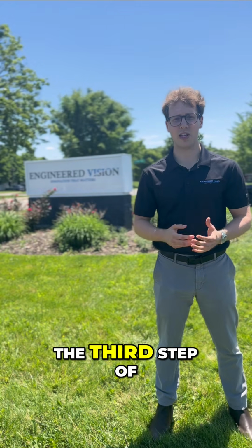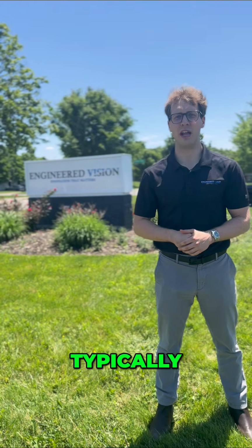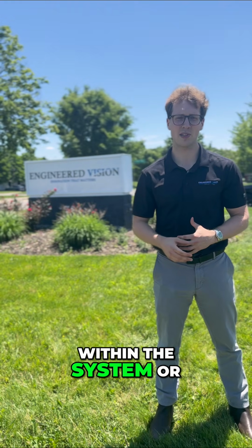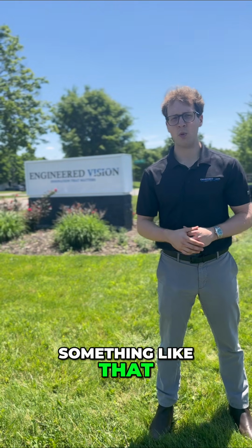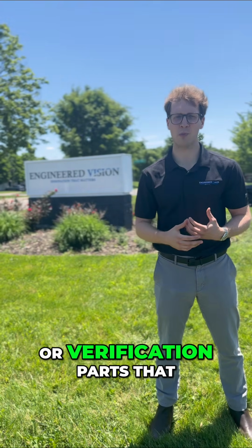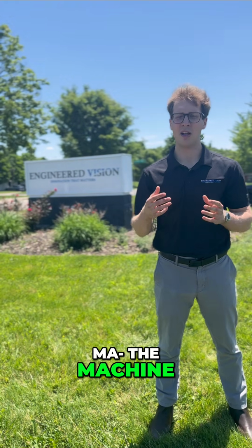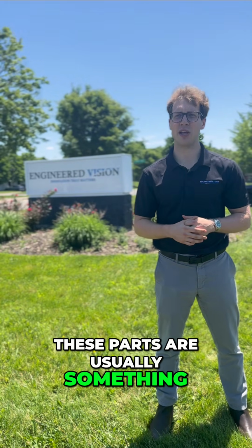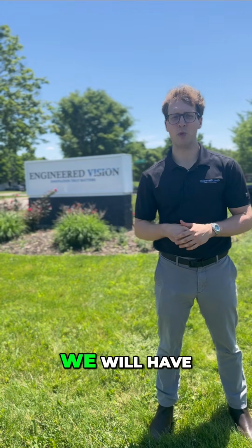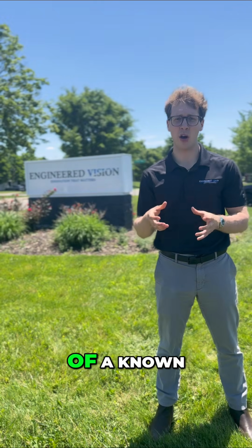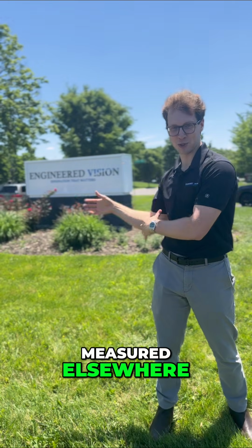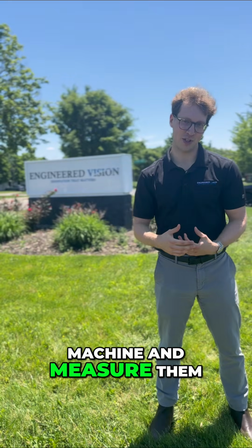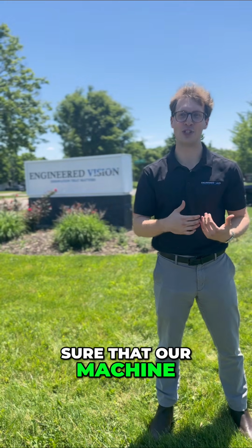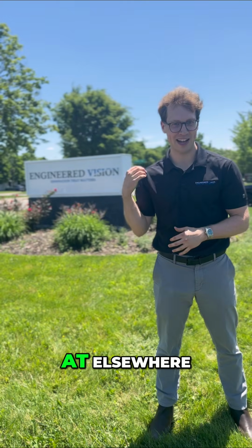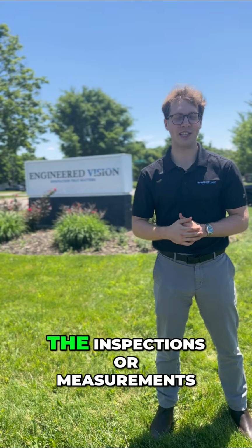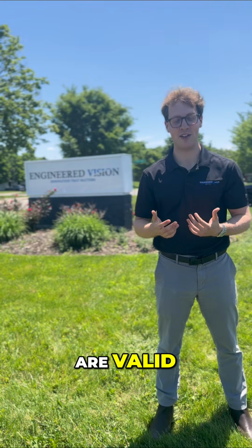And then the third step of that is typically if we are taking some sort of measurements within the system or doing an inspection or something like that, we will have some sort of master parts or verification parts that we will run through the machine. These parts are usually, for example, if we're taking a measurement, verification parts of a known measurement measured elsewhere. And then we will run them through our machine and measure them. And we will make sure that our machine is measuring what they were measured at elsewhere to make sure that the inspections and measurements that we're doing are valid.